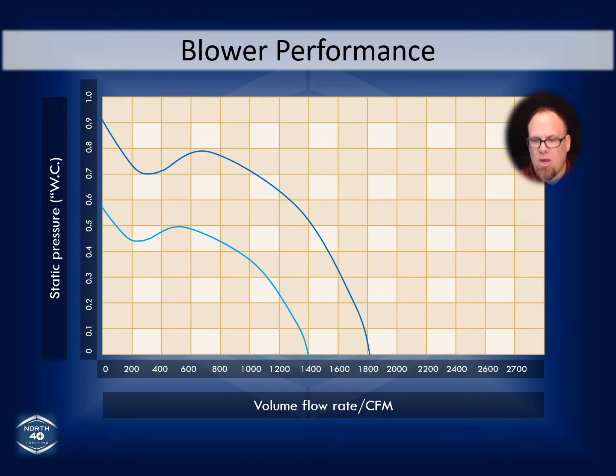That's taking the blower out of the furnace altogether and setting it out on the floor. It's equally as bad for the motor. It's going to burn itself out because it's freewheeling, but you get my point. Least amount of resistance, so we got 0 resistance, is the highest amount of airflow. So look at it this way.